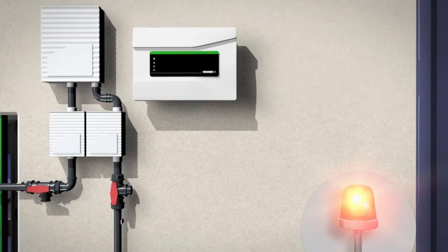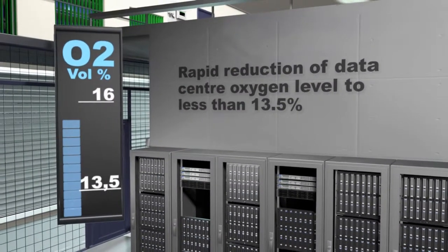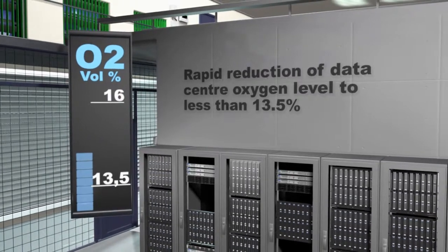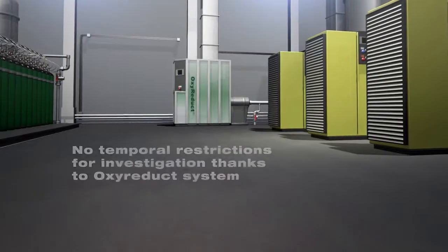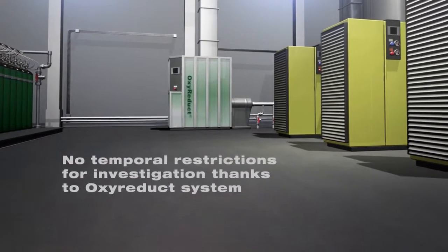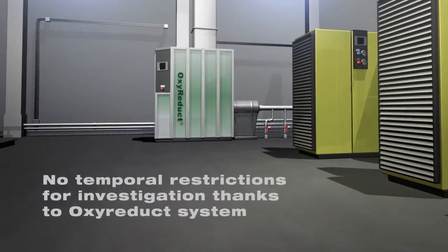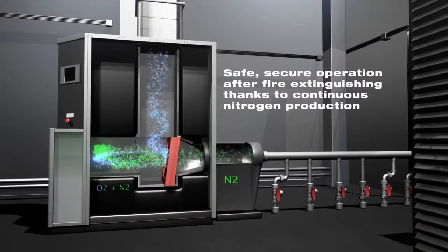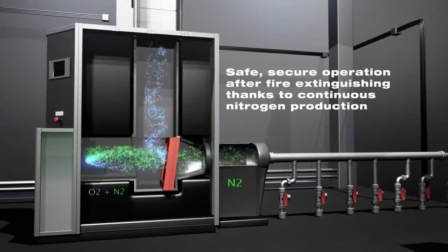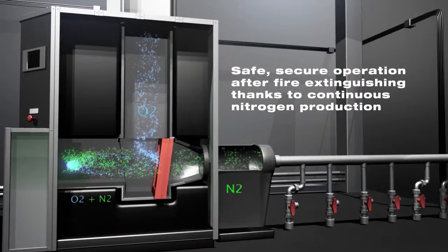If the fire risk does not decrease, the oxygen volume is rapidly reduced even further, to a level of 13.5%. This low level can be maintained for any amount of time using the OxyReduct units, providing ample time to systematically investigate the causes and location of the fire. Where conventional data centers have a period of vulnerability after an incident while the nitrogen tanks are being refilled, the data center Nuremberg 6 continuously produces its own supply of nitrogen.